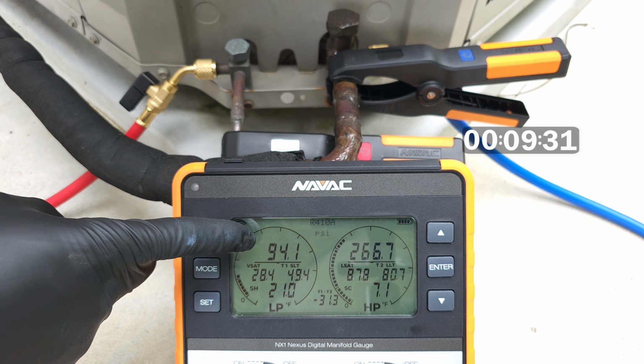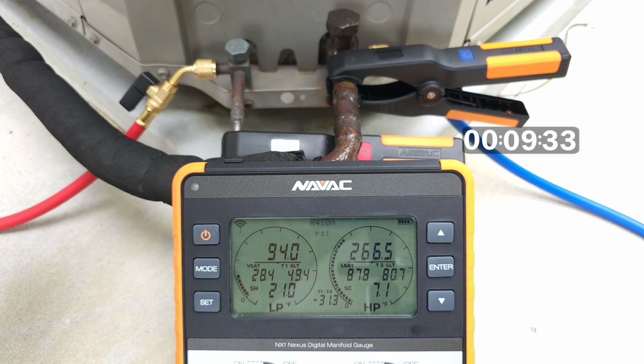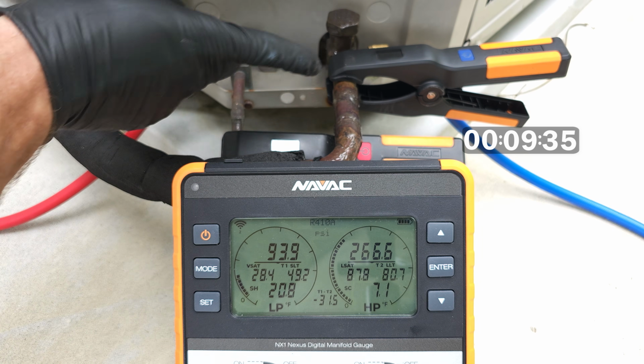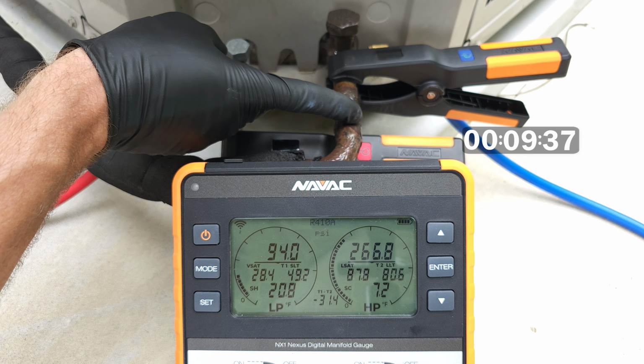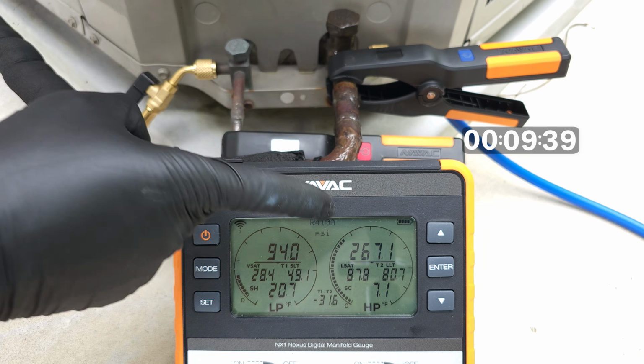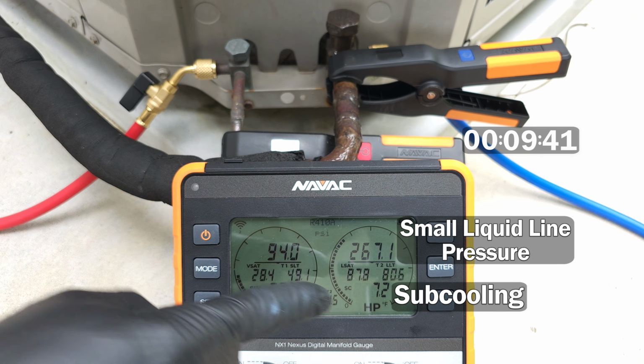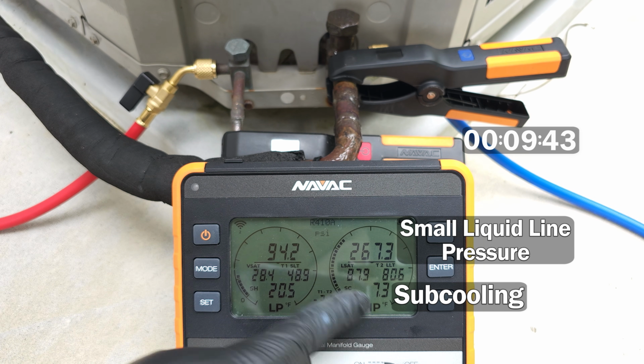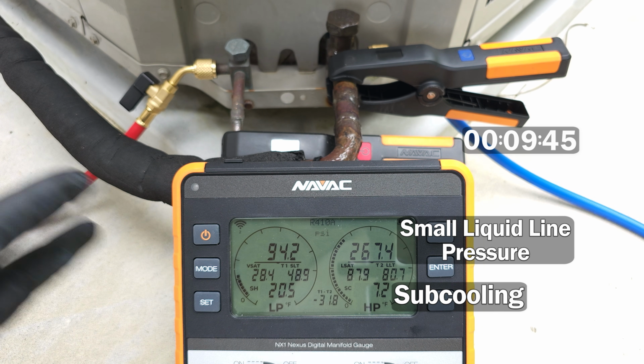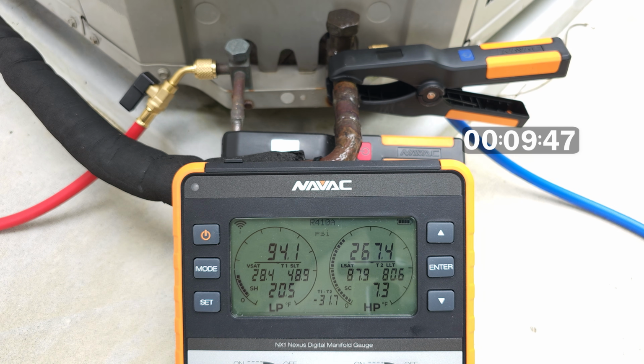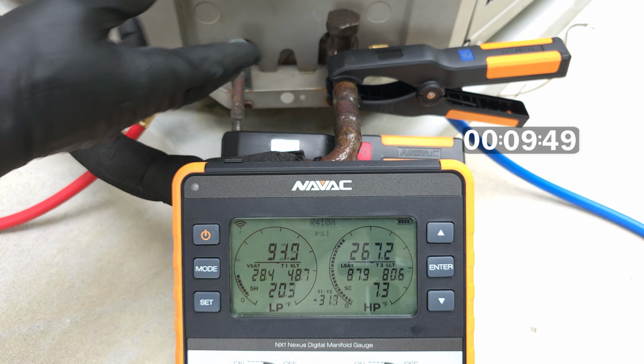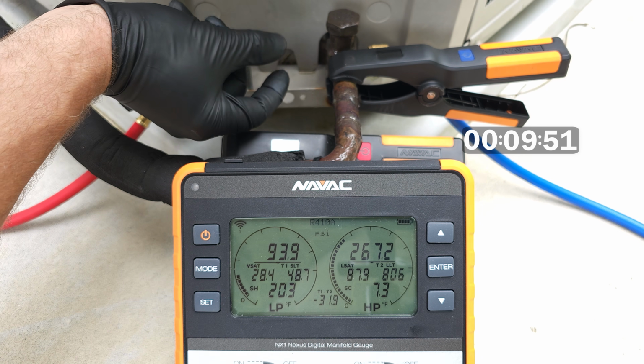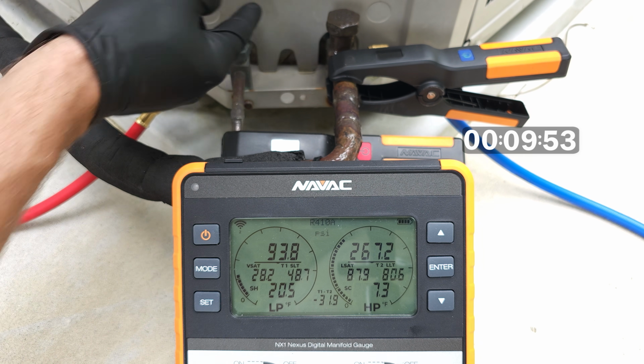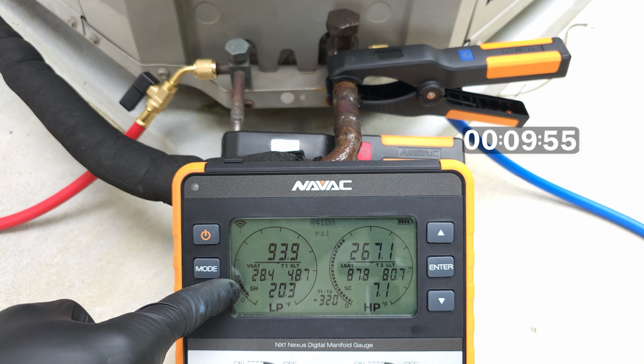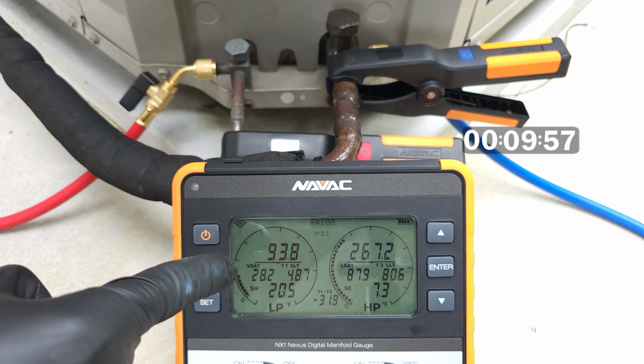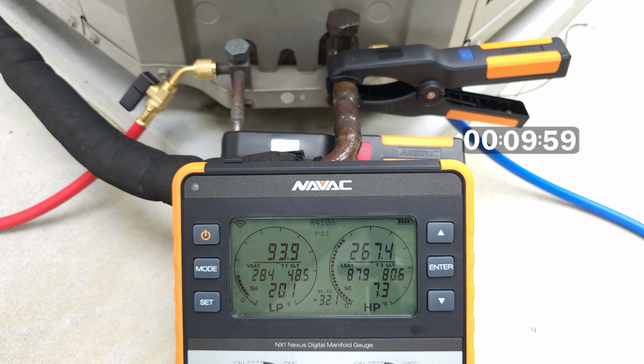This system has a thermostatic expansion valve. It's not going to allow more refrigerant into that indoor coil just because we put more refrigerant into the system. The only thing that would happen if we added refrigerant is this pressure is going to increase and the subcooling is going to increase. That's it. It's going to become less efficient because we have more liquid stacked in the outdoor unit and less of a phase change area in the outdoor unit. We have to measure airflow before doing this. Before measuring the refrigerant charge, you have to measure airflow.